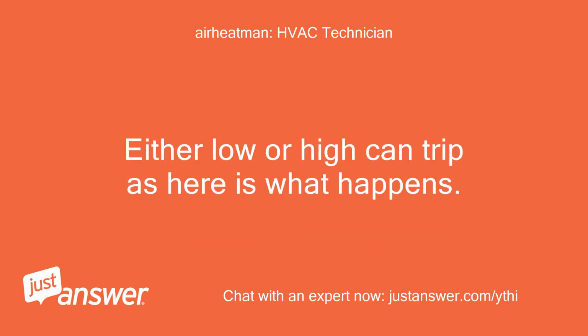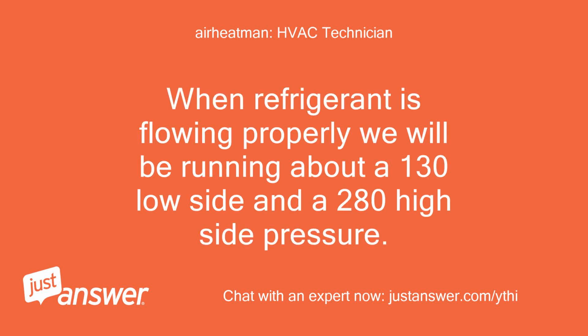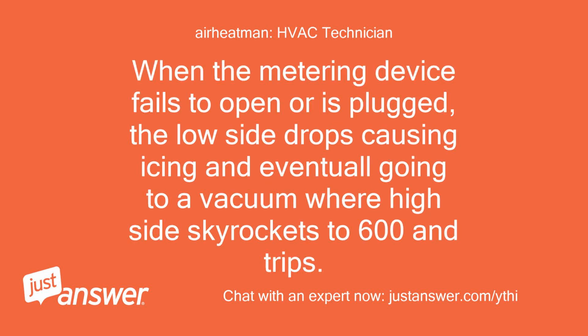Either low or high can trip, as here is what happens. When refrigerant is flowing properly, we will be running about a 130 low side and a 280 high side pressure. When the metering device fails to open or is plugged, the low side drops, causing icing and eventual going to a vacuum where high side skyrockets to 600 and trips.